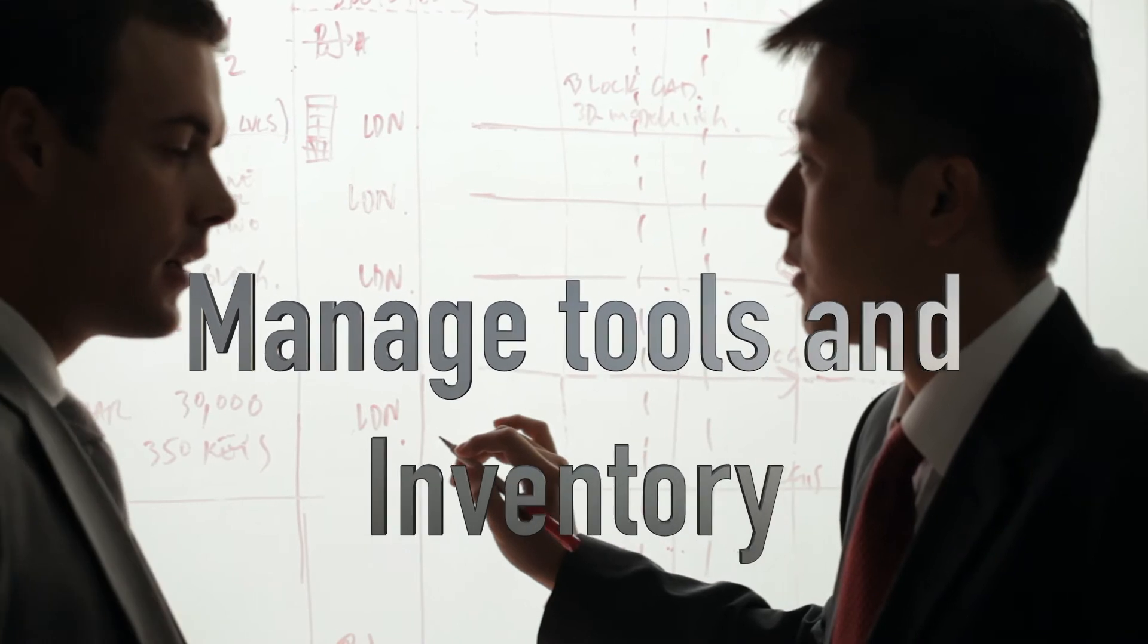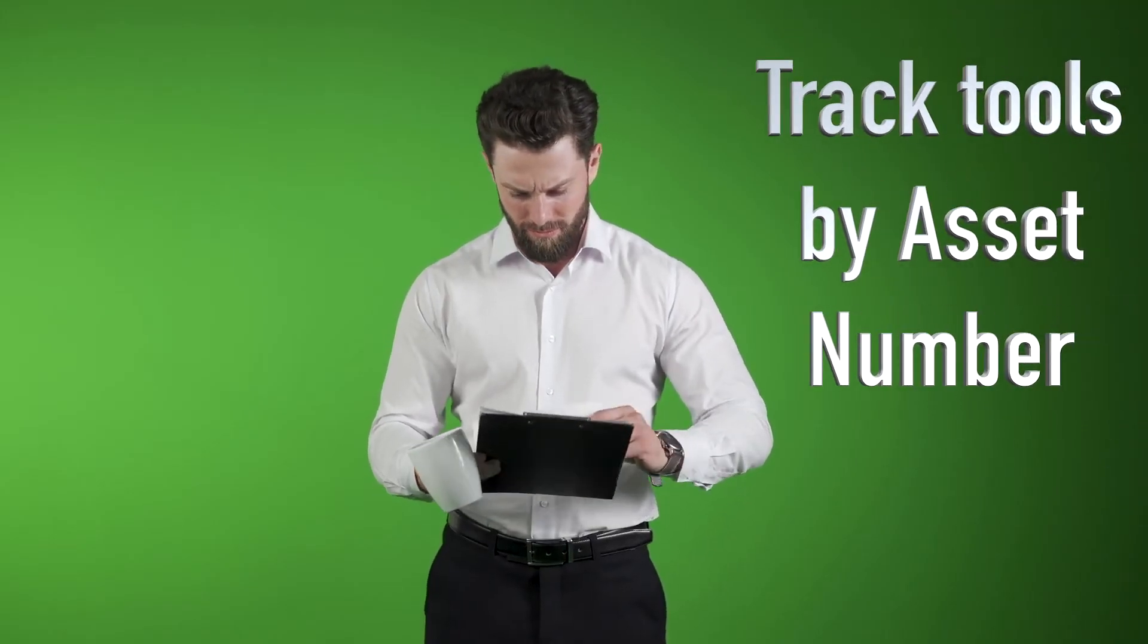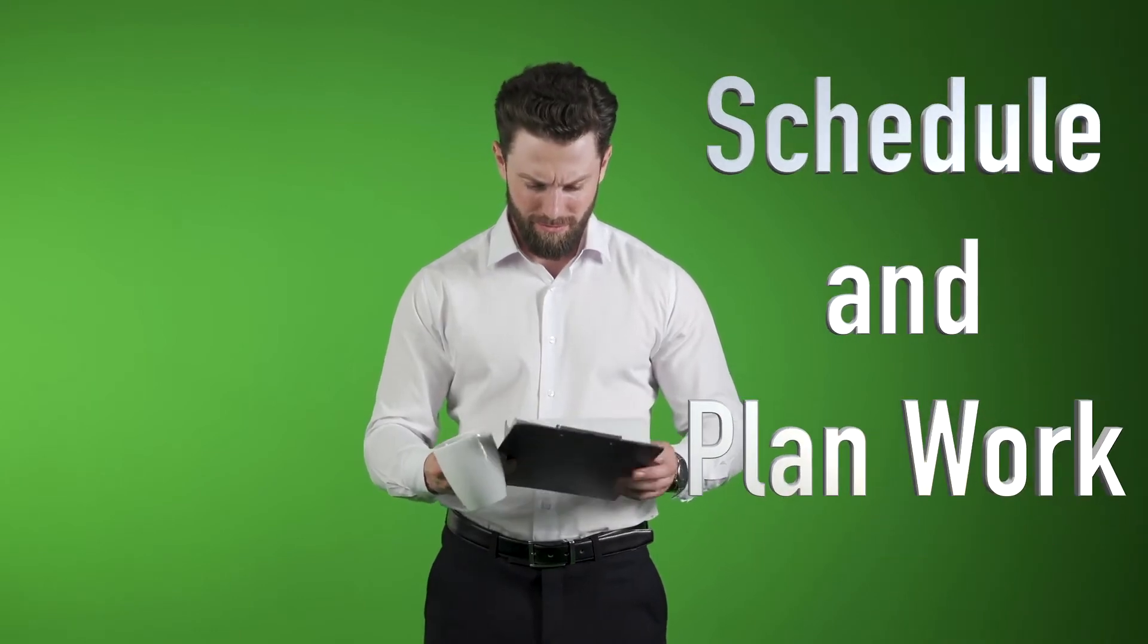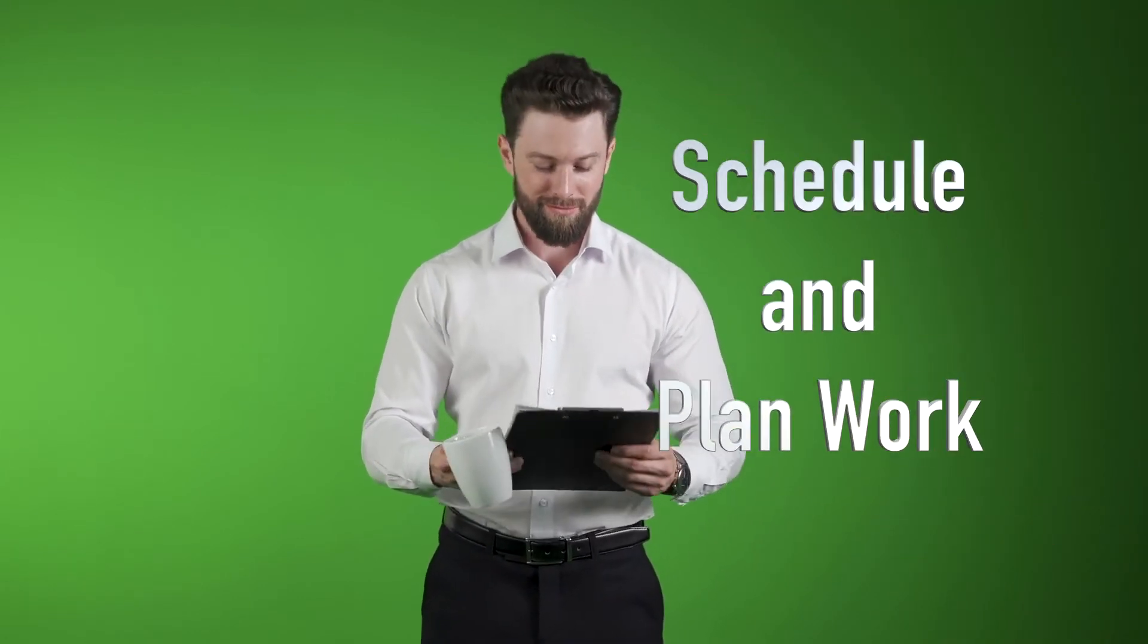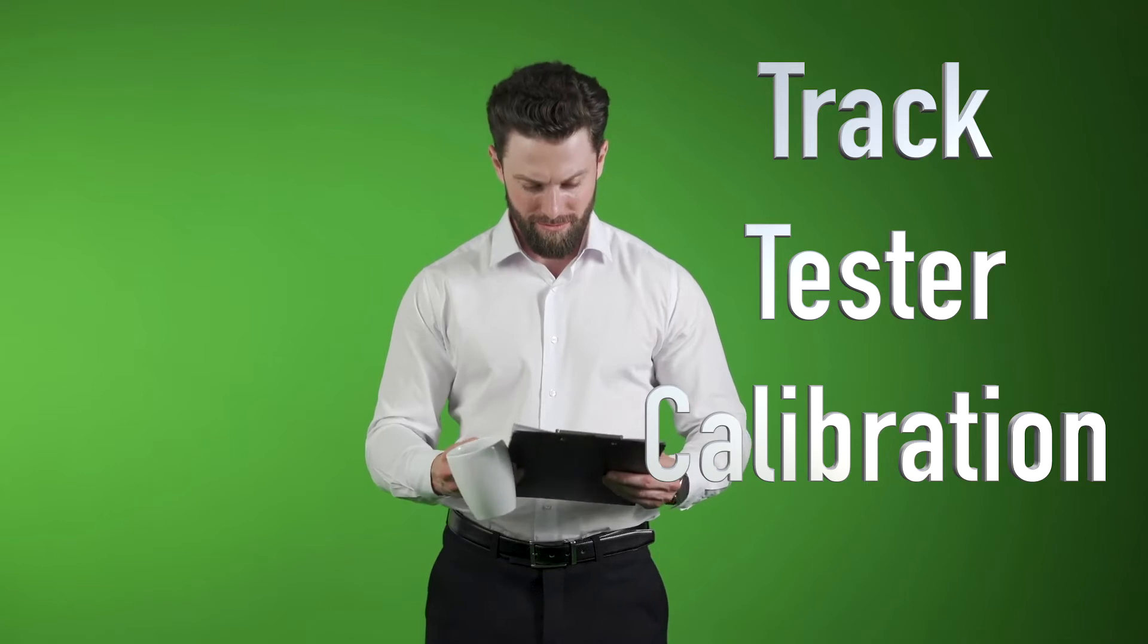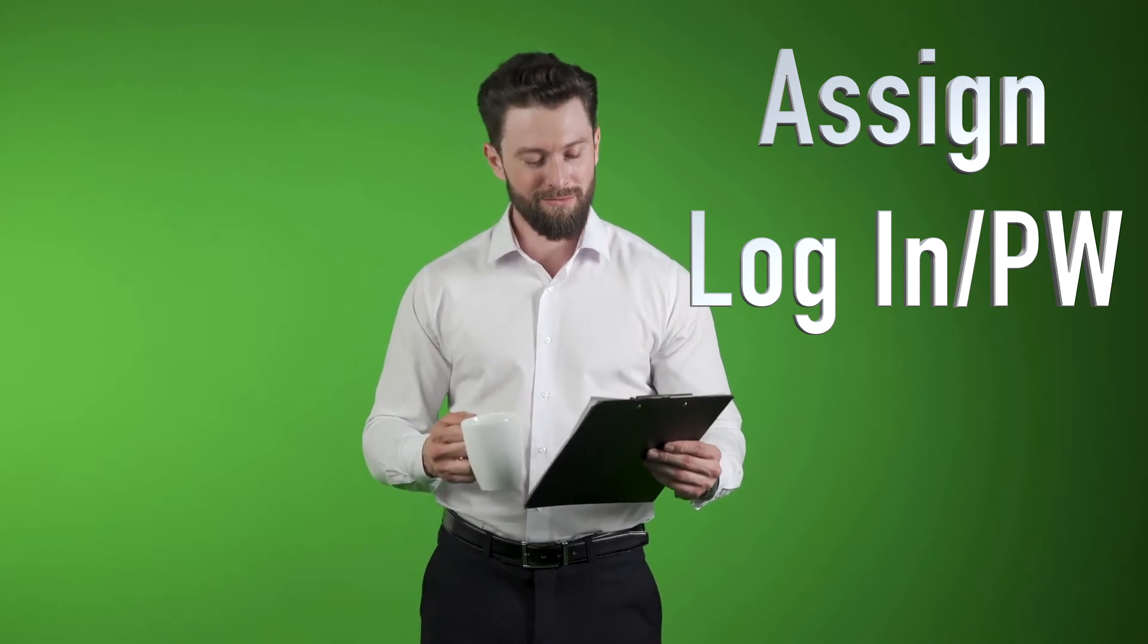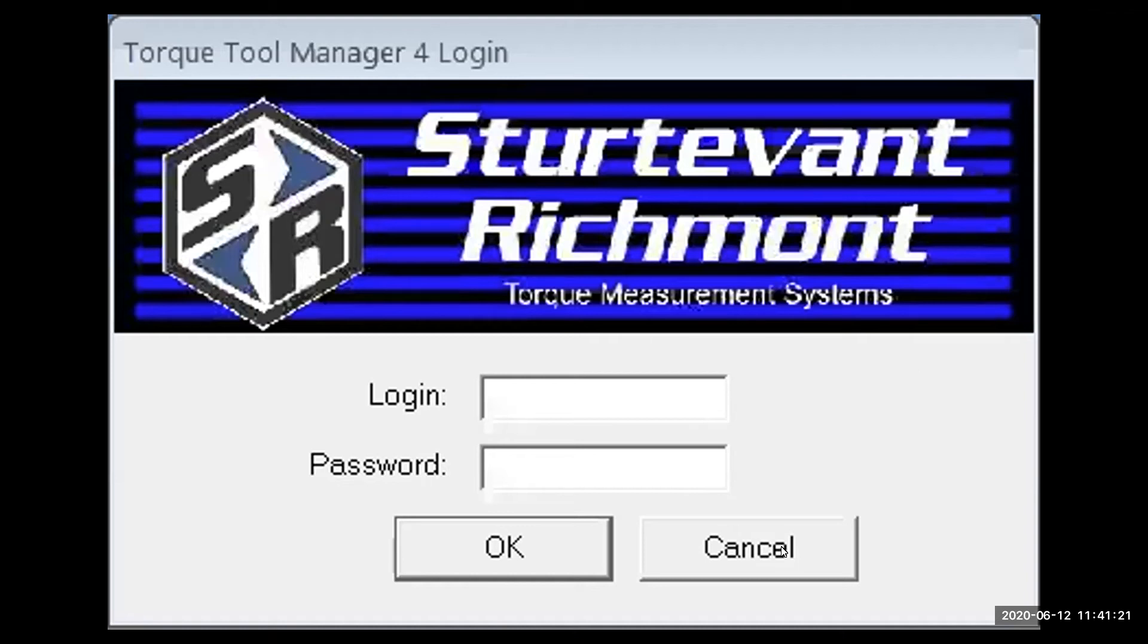TorqueToolManager 4.0 will manage all of your tools and the inventory. It'll help you track calibration dates, when it was last calibrated, and what's next. It'll help you track by asset number. Do you have tools that are inactive but still need to be tracked? The database can do that for you. It can also help you schedule and plan so that you know how many tools and what kind and when they're coming. It also helps you keep track of the calibration on your torque testers and the transducers that go with those testers. It allows you to assign staff members different levels of responsibility and different tasks.